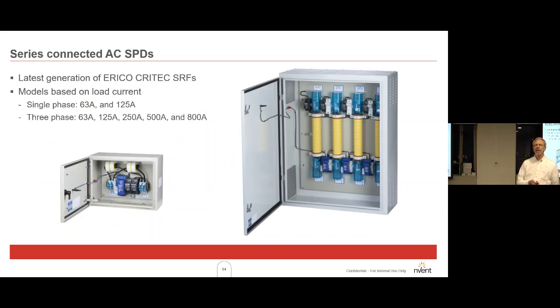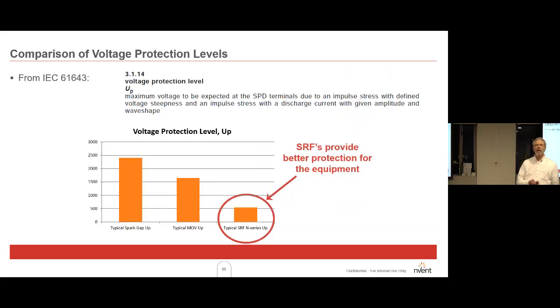Series connected surge diverters, otherwise known as filters, put an inductance in series with your load current. This is showing your voltage protection level when one of those is used. UP is the voltage that's allowed through after the surge diverter has acted on the surge. A typical spark gap on the left still lets through nearly 2,500 volts, which is quite high. A typical metal oxide varistor would be more like 1,600 volts, and a typical surge filter is right down at just over 500 volts. So they're particularly effective, but they are relatively expensive because you've got to size them according to your load current.